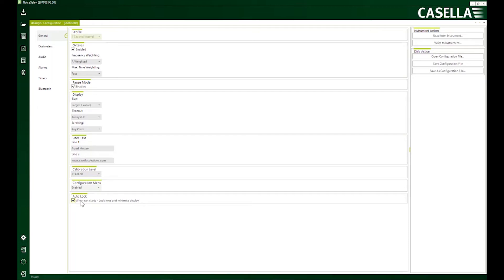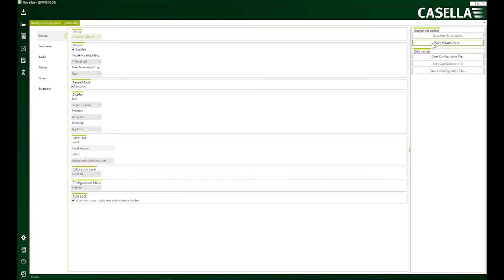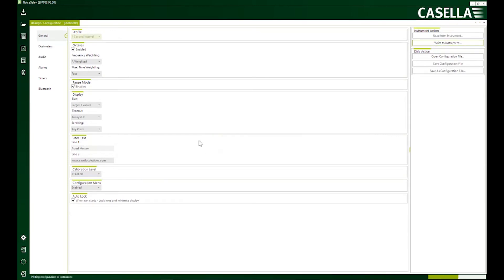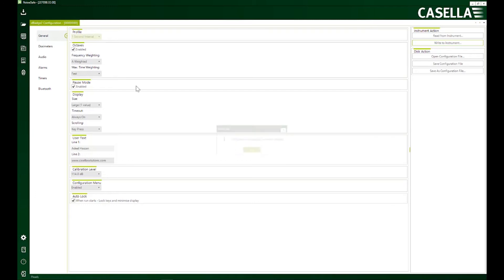Auto lock is to avoid any human error. If this is selected, then the keys will get locked as soon as the device goes into the run mode. So if you make any of these changes, make sure to save it by clicking on write to instrument button. All right. So I'm going to move down the list.